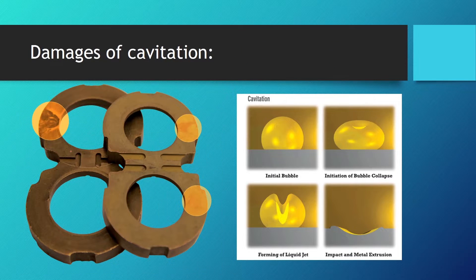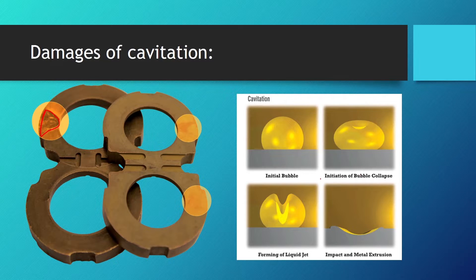Here we can see a picture of a gear pump that had cavitation — a big chunk of metal was damaged, and this is not something that happens in a second. Cavitation damages your components over time. We can see the vapor bubble, and when it gets into a place of higher pressure we have the initiation of the bubble collapsing in on itself, and there we have the formation of the liquid microjet which hits our components and damages our pumps.